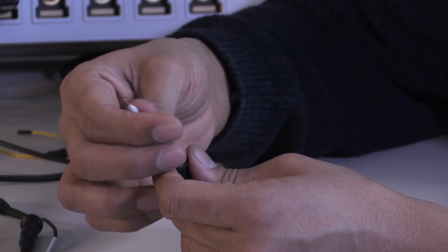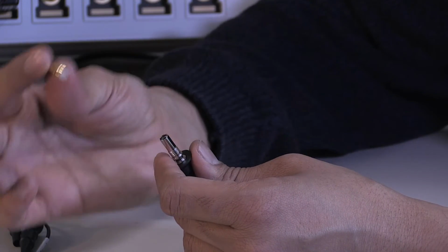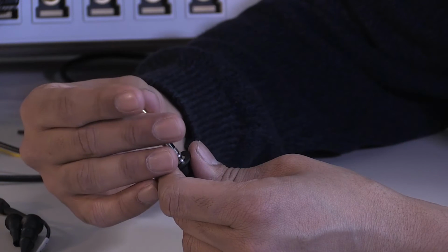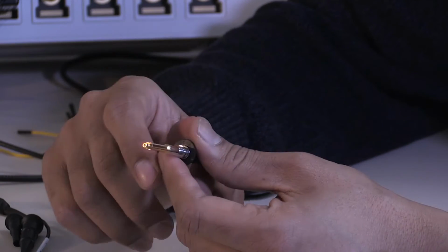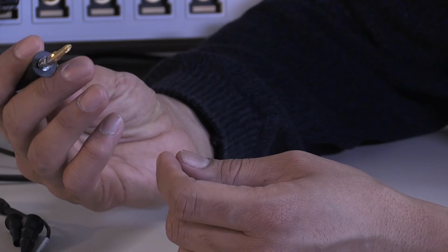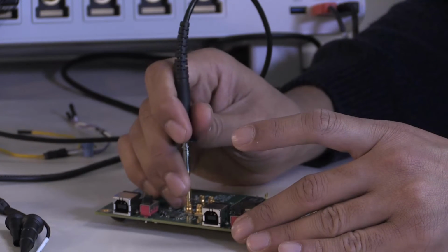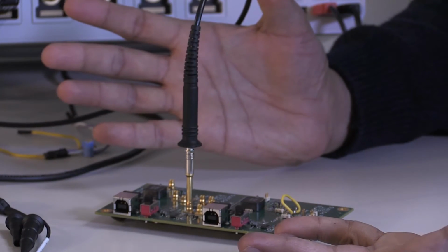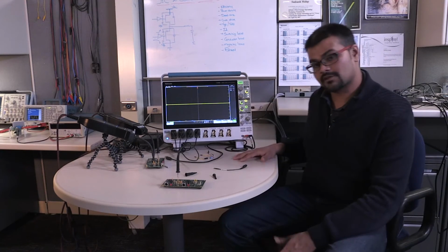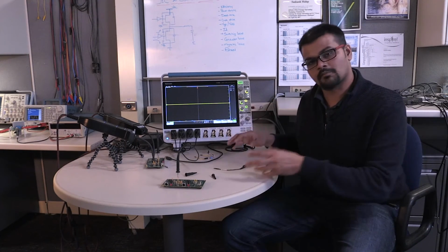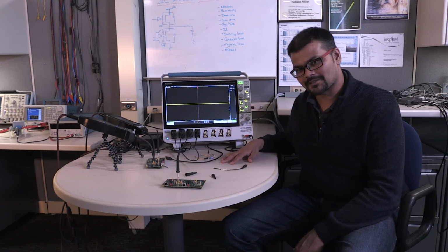So this is pretty cool. What we did was we created an adapter. This is an MMCX adapter for the standard TPP1000 probes, and you essentially plug it in and you have this beautiful high frequency connector. So once you have these connectors, you can essentially just plug it in, and there you have it. In summary, this is pretty much all the instruments we have for these measurements. We'll bring in some more stuff as we go through the sessions, but let's get rolling and look at the measurements.